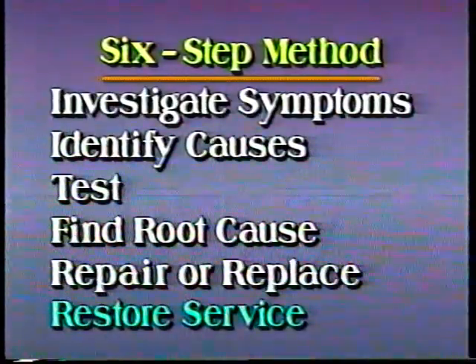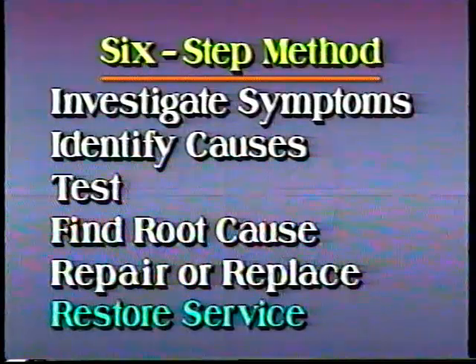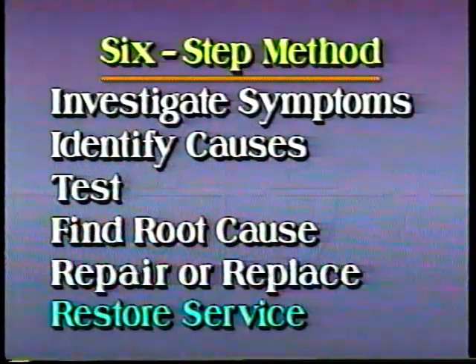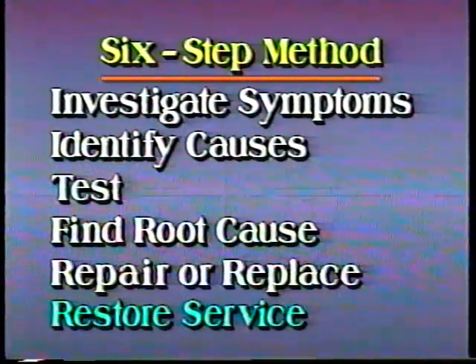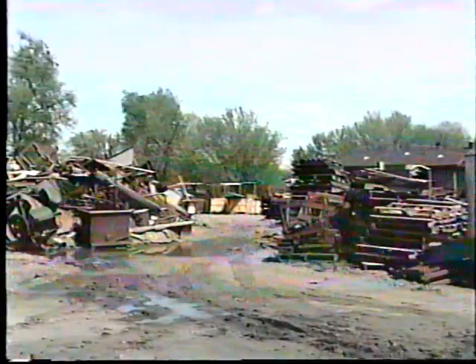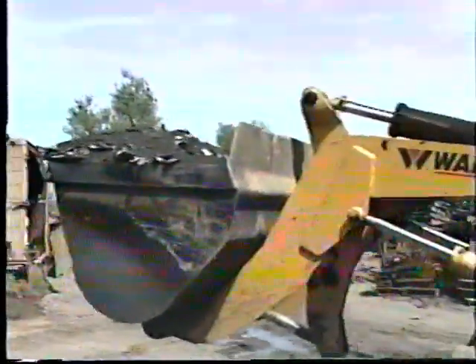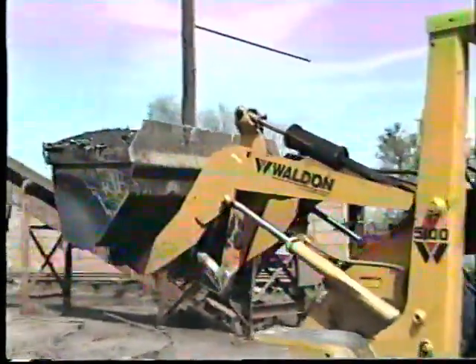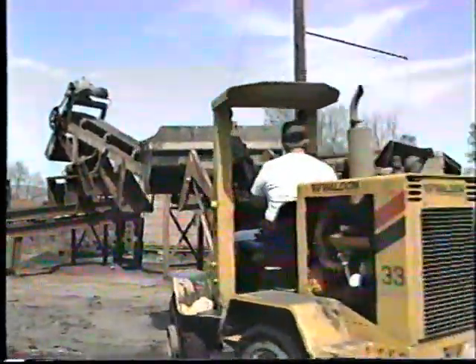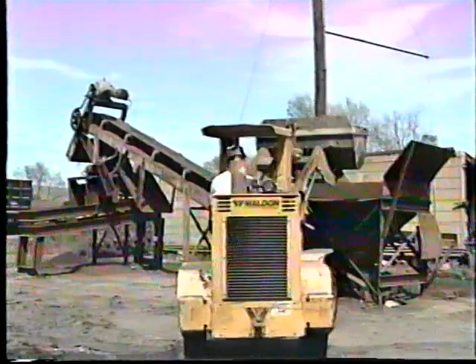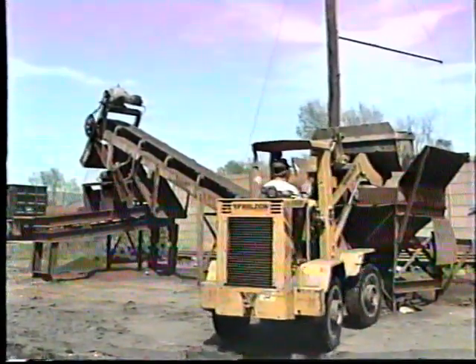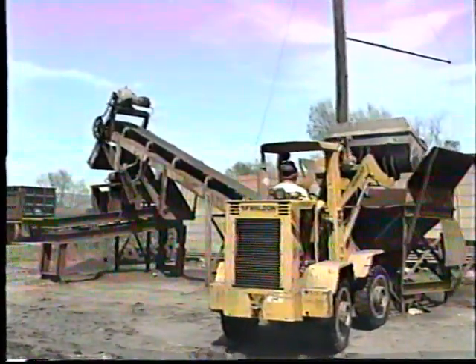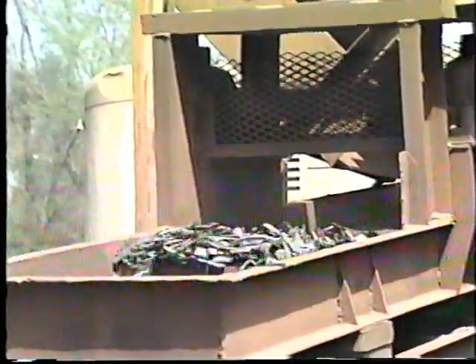Once the direct cause and the root cause have been corrected, the last step in the 6-step method is to perform a final test of the system's operation before returning it to normal service. Be certain that all guards are in place and that all personnel are clear before restarting the machinery. Observe the unit running. Look, listen, smell, and feel. Make whatever adjustments are necessary until you're satisfied that the unit is operating properly.